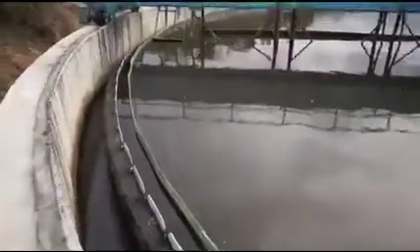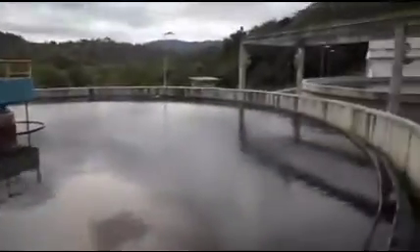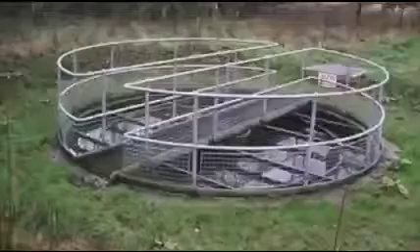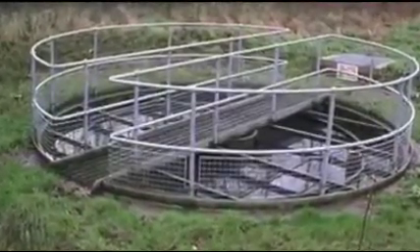The next step is another settling tank like that used in the primary treatment. This time, the goal is to remove the bacteria used to degrade the waste. A portion of the sludge collected is sent back to the secondary treatment step to maintain the community of bacteria that degrade the waste. It's a careful balance.